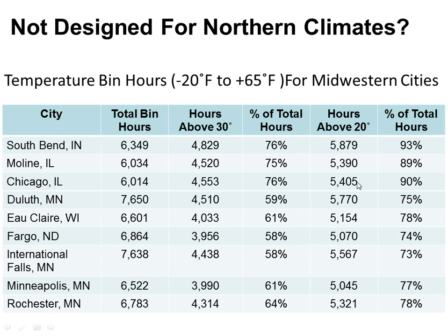If you look at hours above 20 degrees, which is really kind of the range we're going to get into with these extreme and Greenspeed heat pumps, 5,400 hours are above 20 degrees, so between 20 and 65 degrees outside, which means 90% of our heating hours are above 20 degrees outside. So if I got a heat pump that can handle lower temperatures like one of these Greenspeed or extreme heat pumps from Bryant and Carrier, I can handle pretty much 9/10 of my year that way, and only 10% of the hours do I have to run my furnace.